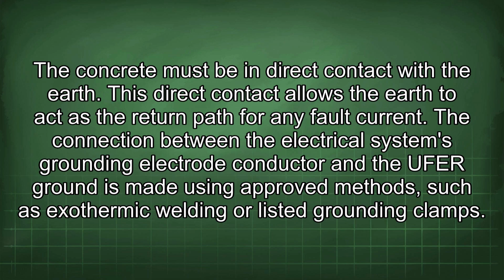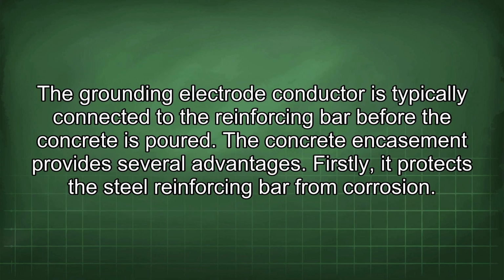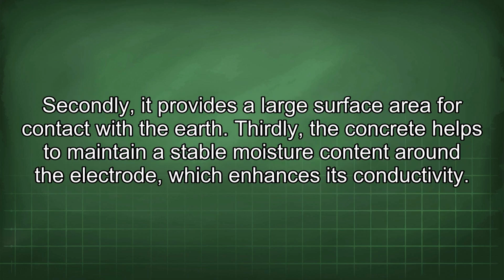The connection between the electrical system's grounding electrode conductor and the UFER ground is made using approved methods such as exothermic welding or listed grounding clamps. The grounding electrode conductor is typically connected to the reinforcing bar before the concrete is poured. The concrete encasement provides several advantages. Firstly, it protects the steel reinforcing bar from corrosion. Secondly, it provides a large surface area for contact with the earth. Thirdly, the concrete helps to maintain a stable moisture content around the electrode, which enhances its conductivity.